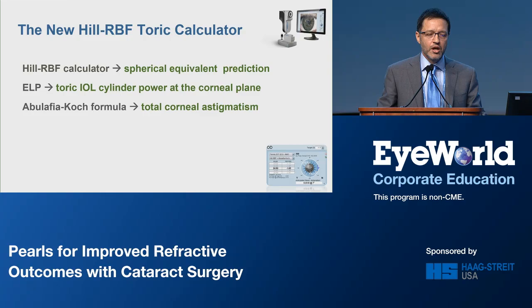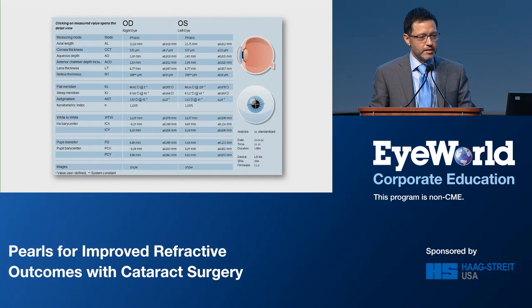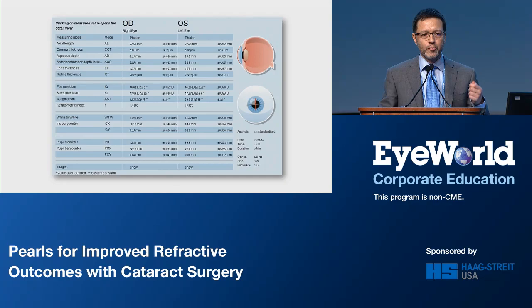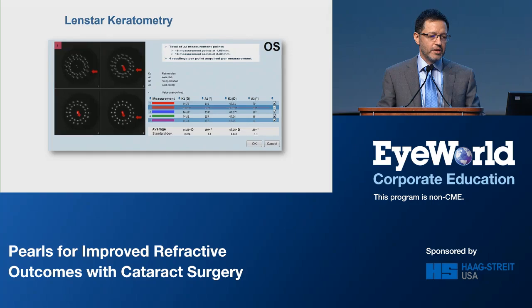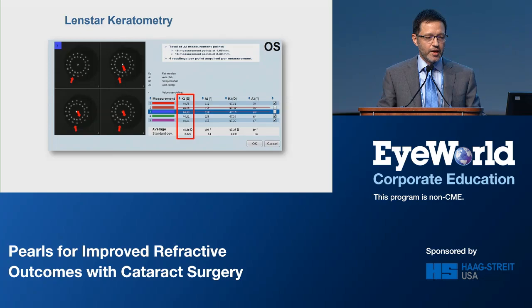The LenStar is not just like a black box where you push buttons and get numbers. You can actually see the measurements, go quickly through them, and delete the ones that you don't like, giving you a new set of Ks with standard deviation both for the flat K and the steep K, and also for the steep meridian, which is very reassuring.